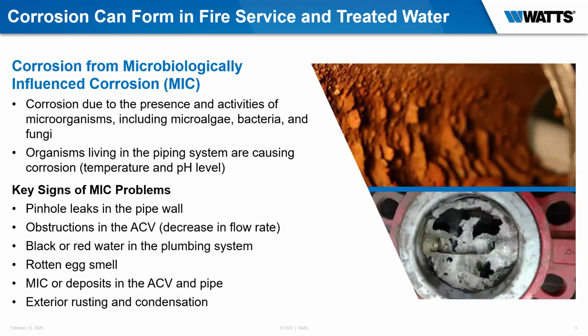Corrosion can form in fire systems and treated water. A big area is MIC, due to the presence of microorganisms. These organisms live in the piping system depending on the temperature, the pH level, and the amount of oxygen in the water. We'll talk more about that later. Everybody's seen MIC. It's probably the most identifiable and leads into corrosion problems.